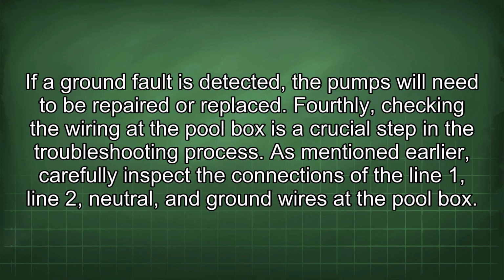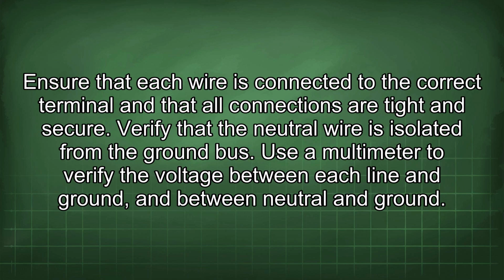Fourthly, checking the wiring at the pull box is a crucial step in the troubleshooting process. As mentioned earlier, carefully inspect the connections of the line 1, line 2, neutral, and ground wires at the pull box. Ensure that each wire is connected to the correct terminal and that all connections are tight and secure. Verify that the neutral wire is isolated from the ground bus. Use a multimeter to verify the voltage between each line and ground, and between neutral and ground.